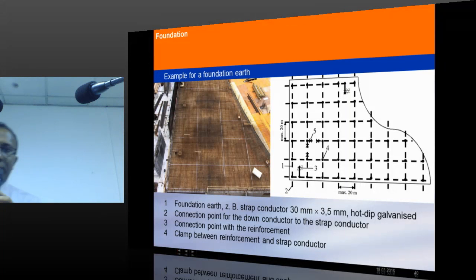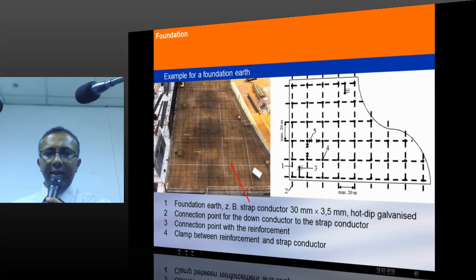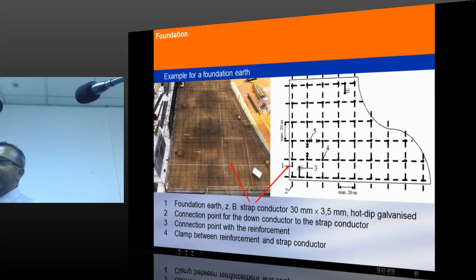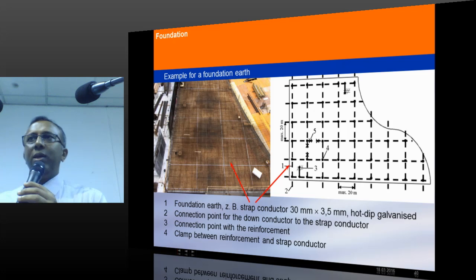And you see, in a building, foundation earth with a strap conductor. So this is the complete foundation, but the additional strap conductors are ready every, I think, about 5 meter or every 10 meters. Some values are given in the standard. And this whole mass, steel mass, will do the job of dissipating the current, provided, as I explained earlier, there is no insulation between the foundation and the soil.